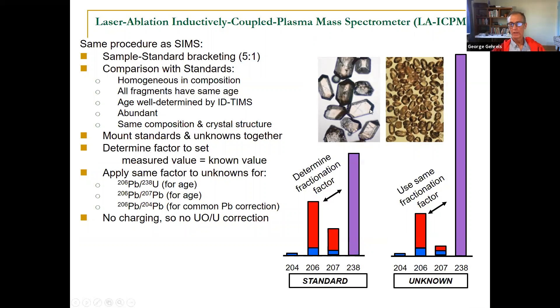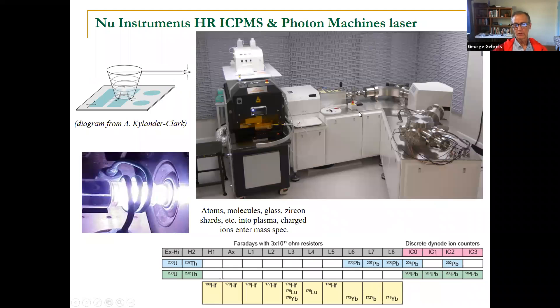Turns out laser ablation ICPMS works exactly the same. We have the same standards, the same unknowns. We do standard sample bracketing. The precision that we get is about the same, also one to 2%, something like that. And so here's the instrument that we use. This is still basically two different instruments. There's the laser on one side and the mass spectrometer over here. And the connection between the two is this tiny little Teflon tube.